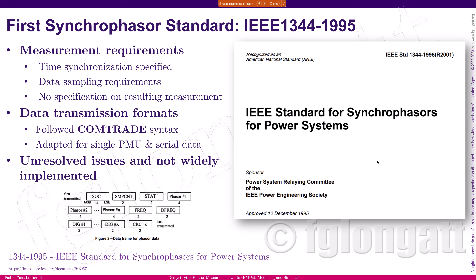The 1344 standard was succeeded by what we know today as ANSI C37.118, the IEEE standard for synchrophasors in power systems. This standard is divided into two parts: C37.118-1, which covers measurement, ROCOF, and dynamic operation, and C37.118-2, which covers data exchange along with improvements regarding flags and configuration. Both standards together cover what we know today as synchronized phasor units.